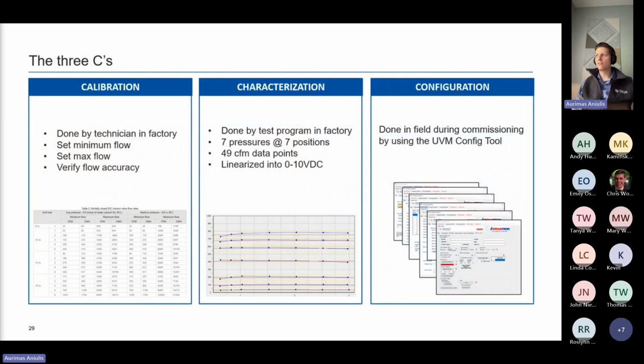Now, there are the 3 C's that are kind of used in this space, and it's important that we all understand them, and that's calibration, characterization, and configuration. Calibration is us taking our equipment and calibrating it so it meets our published spec. Characterization is what we do on each individual air valve to capture its unique flow data sets. And you'll see that 2 identical valves will have minor flow deviations by 3 to 4 CFM, but still within plus or minus 5 CFM, just because of different metal configurations that are beyond our ability to control. And finally, configuration is something that's done in the field. Now, when you're talking about these scenarios, I hear these 3 words used interchangeably, which no doubt will cause confusion. So it's important to get those understood as we proceed further.